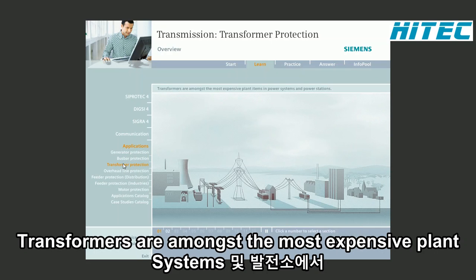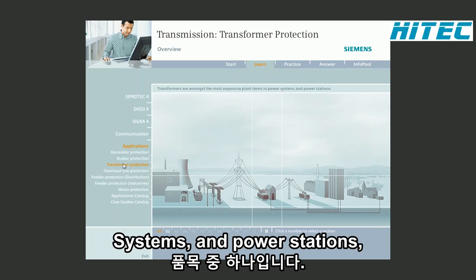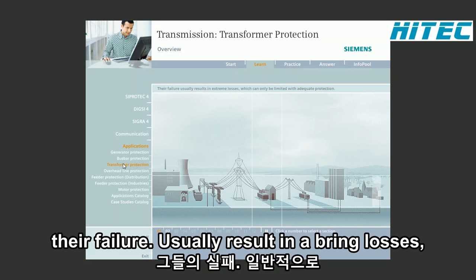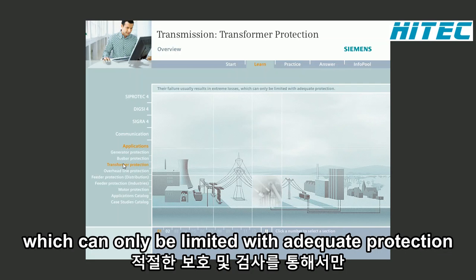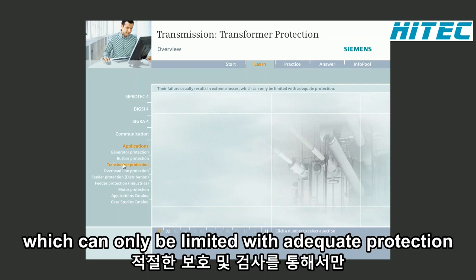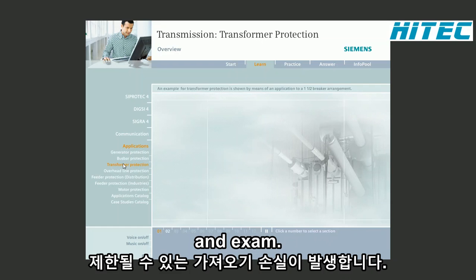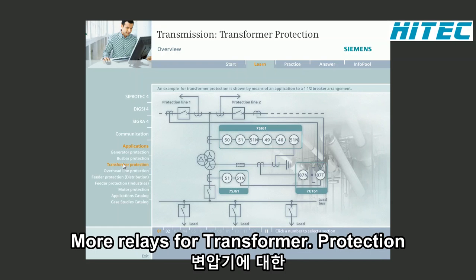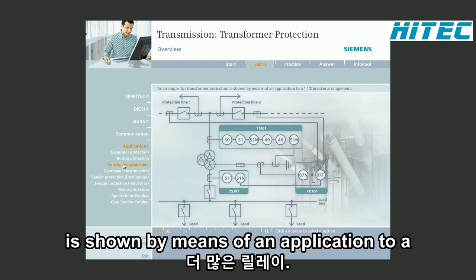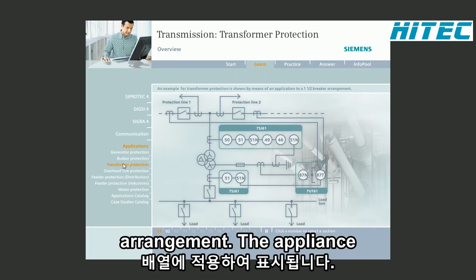Transformers are amongst the most expensive plant items in power systems and power stations. Their failure usually results in extreme losses, which can only be limited with adequate protection. An example of SIPROTEC 4 relays for transformer protection is shown by means of an application to a 1.5 breaker arrangement.